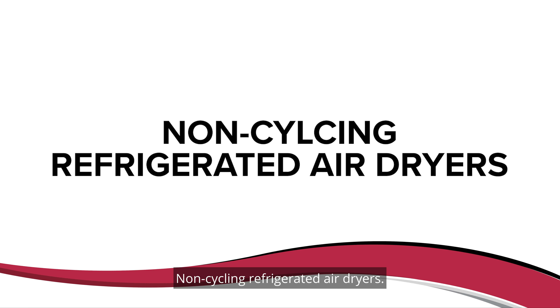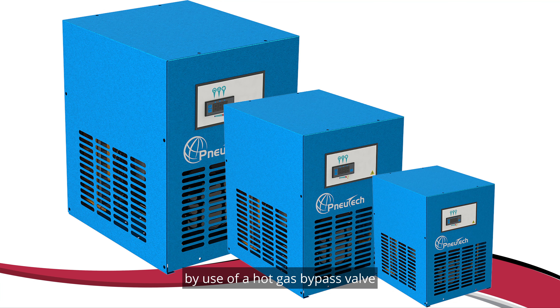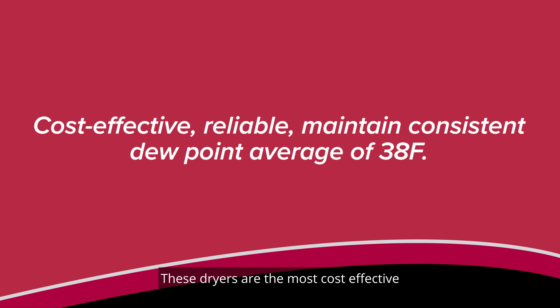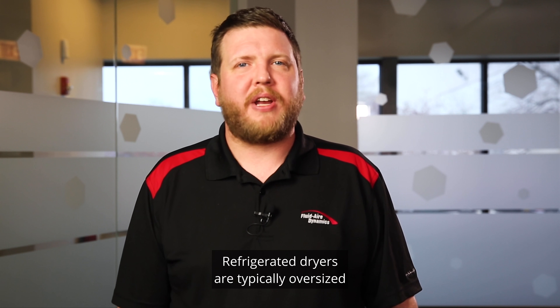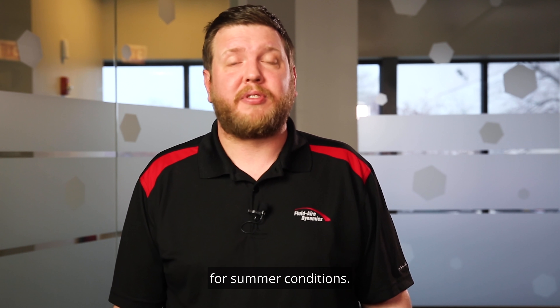Non-cycling refrigerated air dryers allow the refrigeration circuit to run continually. They control their temperature by use of a hot gas bypass valve and cycling of the evaporator fan to maintain a tight temperature range. These dryers are the most cost effective and are typically very reliable, maintaining a fairly consistent dew point average of 38 degrees Fahrenheit. Correction factors can be found on the dryer literature, allowing you to adjust the dryer size for your specific conditions. Refrigerated dryers are typically oversized for summer conditions.